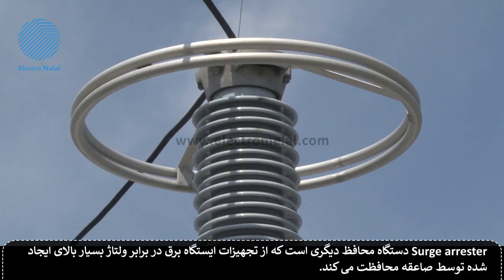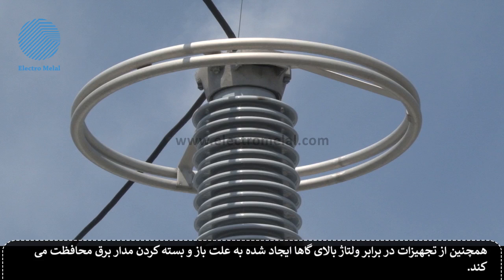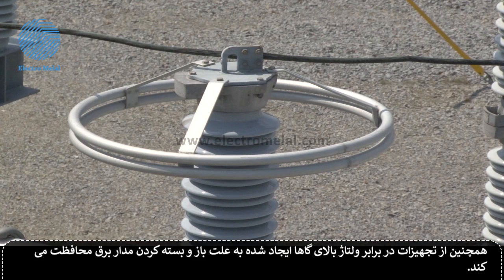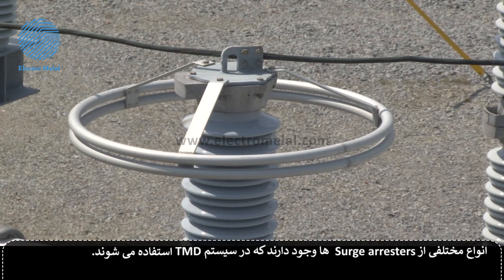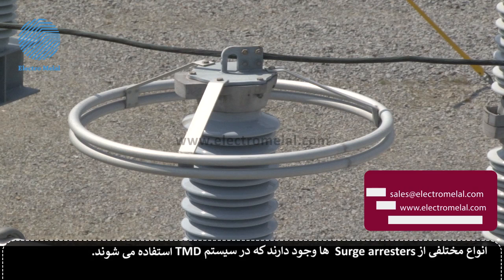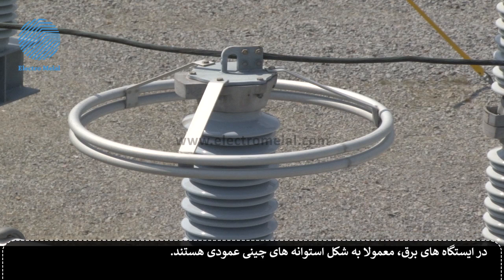A surge arrestor is another protective device. It protects substation equipment from excessive voltage caused by lightning strikes. It may also protect substation equipment from excessive voltage that is sometimes caused by opening and closing circuits. There are a large variety of surge arrestors that are used in T&D systems. In substations, they are generally vertical porcelain cylinders.